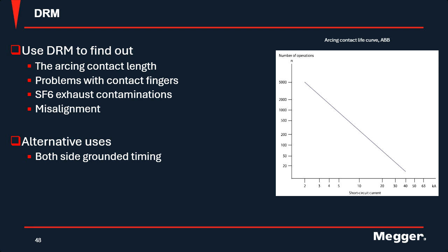So this is a little overview of DRM. The main purpose of it is to find out the condition of your arcing contact and how much length you still have in that arcing contact. It also will find any misalignment, any exhaust contaminants when the air or the oil is forced up into the arcing chamber to help extinguish that arc, and any problems with your contact fingers on that main contact.